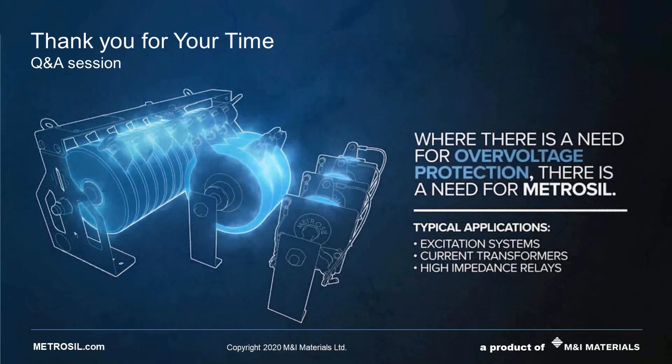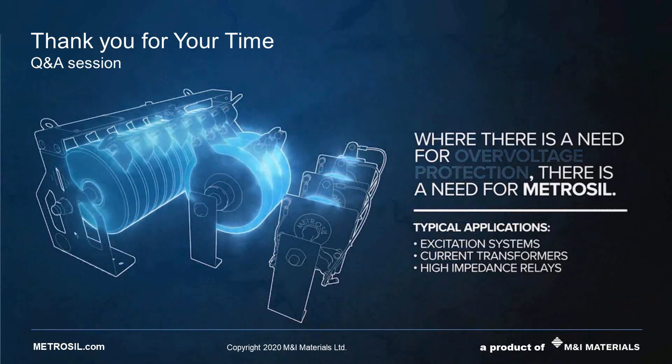Thanks for that, Dom. Thanks to those of you that have submitted questions. The first question I'll put forward to you, Tom, is from Callum, a senior design engineer, who has asked: why not use metal oxide varistors? That's a good question. Metal oxide varistors, or MOVs, are probably the kind of varistor you're most familiar with. Although they're very good for high current applications, they actually have quite poor performance when it comes to high energy capacity. They can tend to explode open circuit, which can cause damage to your coil or the protection cabinet. That's not a problem for silicon carbide varistors. MOVs also tend to degrade every time they're hit, which means you have to keep track with a surge counter — again, not a problem for silicon carbide high energy varistors.